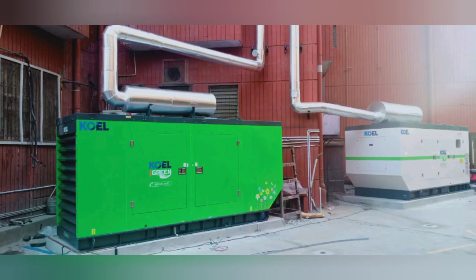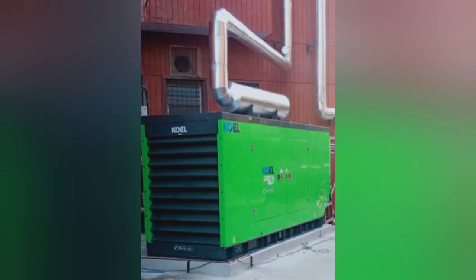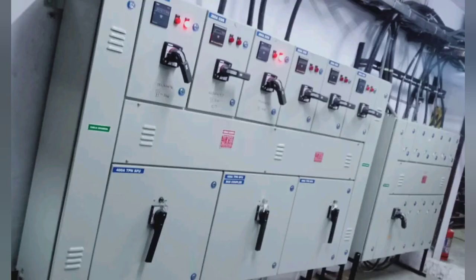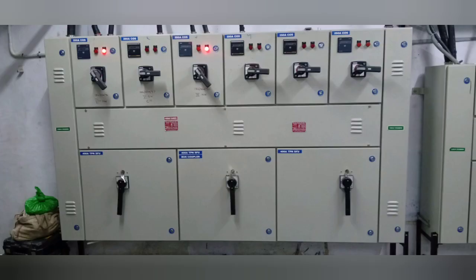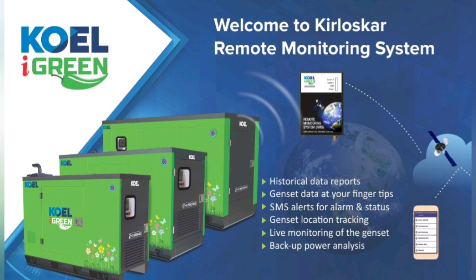These DG sets were supplied recently to one of the commercial complexes in Chennai. This is a 160 kVA KOEL Green automatic genset. Now all the electrical erections are completed. KRM fixing can be planned after completing all the installation works. KRM works on battery supply. To make it function, you need to connect the battery in the genset. Now we have already connected the battery.